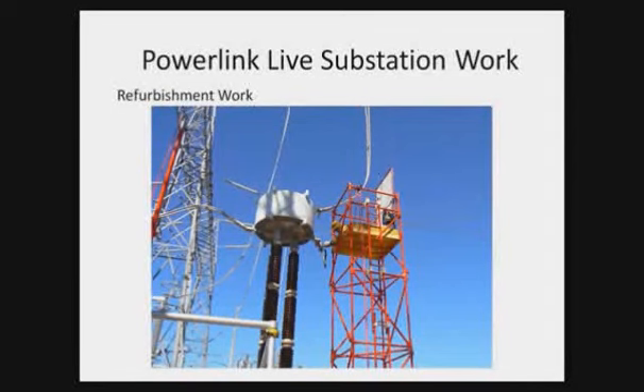So what we do is, from a distance, we actually short out that line trap before we start doing anything on it. And that's what that operator there is doing. He's actually placing a shunt on the bottom side of the line trap. He'll then get moved away, and using hot sticks will actually make the connection to short out that line trap.